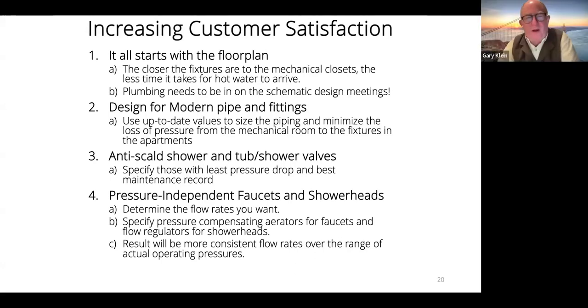The other thing I want to touch on briefly is the design for modern pipe and fittings. The plumbing codes have minimum allowable pressure at different fixtures, right? The critical pressure that you mentioned earlier, Christoph. I think that number is in the 10 to 20 PSI range at the critical fixtures. That was also written down before we had anti-scald shower valves and has never been changed. The observation I would make is that if you only have 20 PSI at your shower valve, you're going to have a really bad feeling shower. It won't work very well because they're designed at 80. It's a problem. We have to work on this as we do the right sizing. We have to make sure we have the right available pressures. So let's go on to the next one.